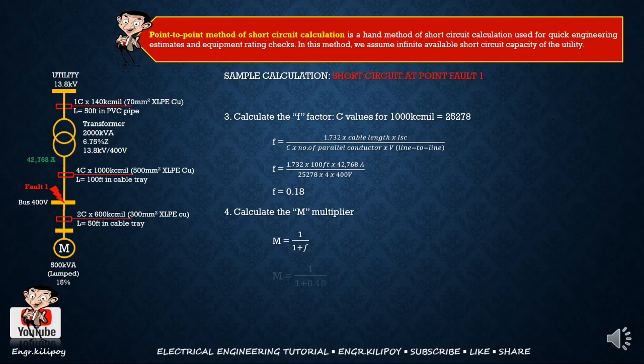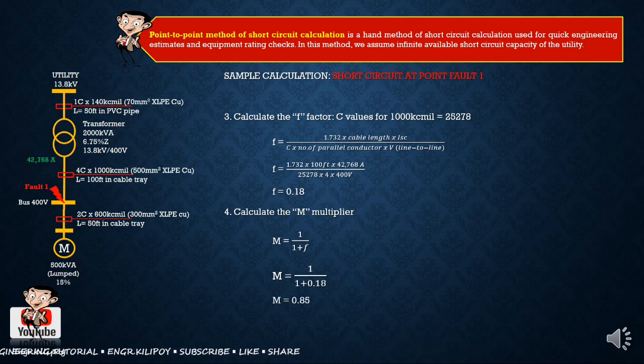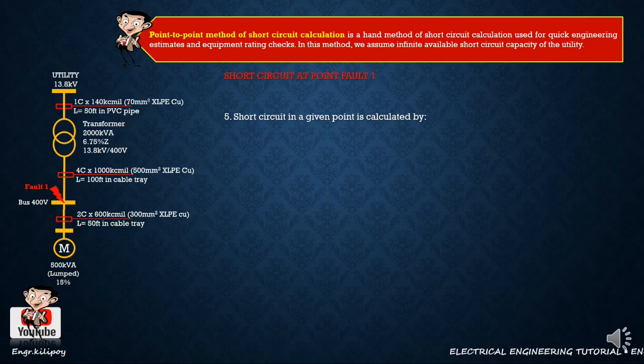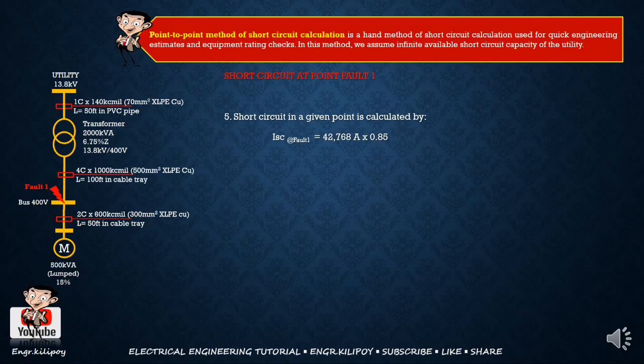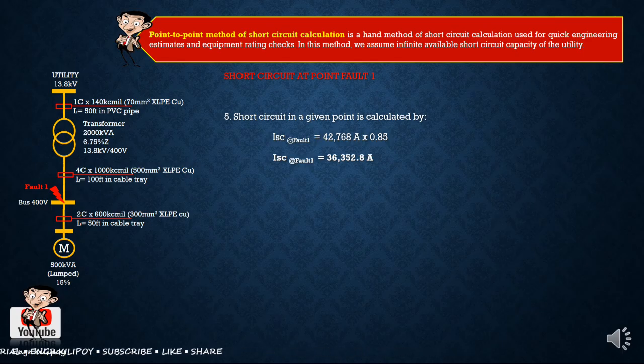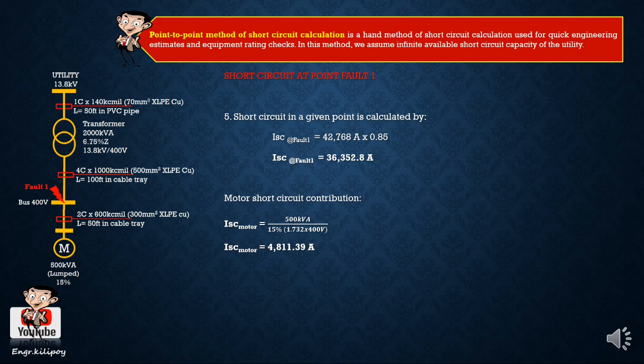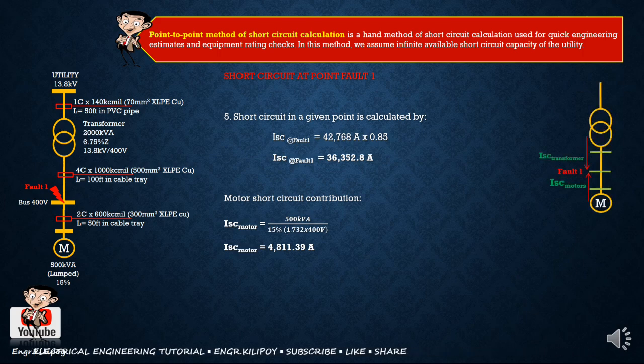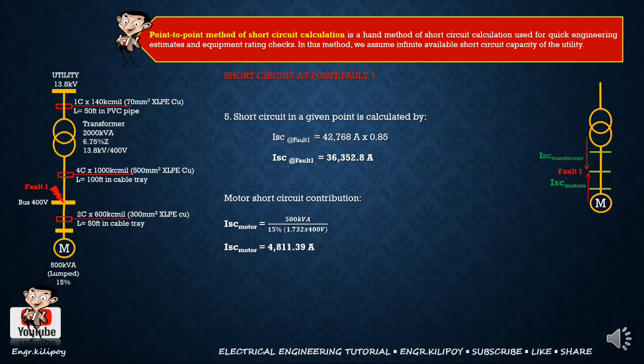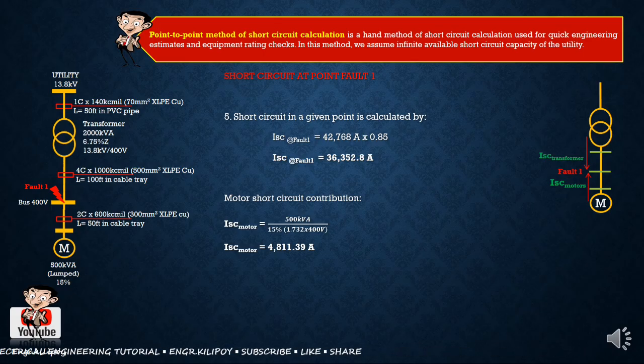It's simply using this formula. So meron tayong 0.85 na M multiplier. Next is short circuit calculation value doon sa fault 1. Dahil meron tayong available short circuit galing sa transformer na 42,768, multiply mo lang sa M multiplier. Meron tayong 36,352.8 ampere. Pero dahil meron tayong short circuit contribution, kung mapapansin mo, from fault 1 pumunta yung short circuit contribution galing dito sa transformer, pupunta sa fault 1, and yung motor contribution pupunta rin yan sa fault point.